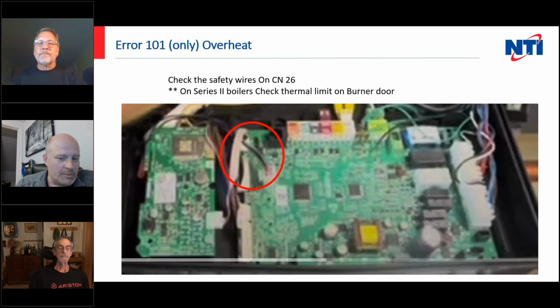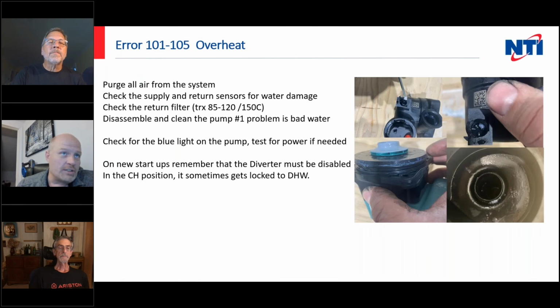Now, the 101 actually means 2 different things. The second thing it means, and the more common one, is that your boiler has overheated in some fashion. So I've grouped together 101 to 105 because they're all basically the same thing. They mean something got too hot. There is a slight variation between them, but realistically it means they got too hot. So you want to make sure all the air is purged. You're going to check your supply and return sensors for water damage. If those sensors get wet, they become more conductive and the boiler's going to read the wrong temperature.